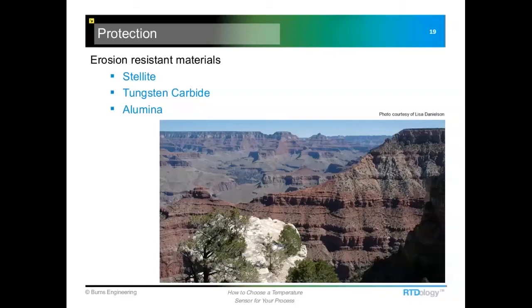And what we did with that one was put in a thermowell that had the stellite coating on it, which lengthened the lifetime by quite a bit, and then they just put a time frame on for replacement of that thermowell probe. So that turned out to be a good solution for that particular customer.